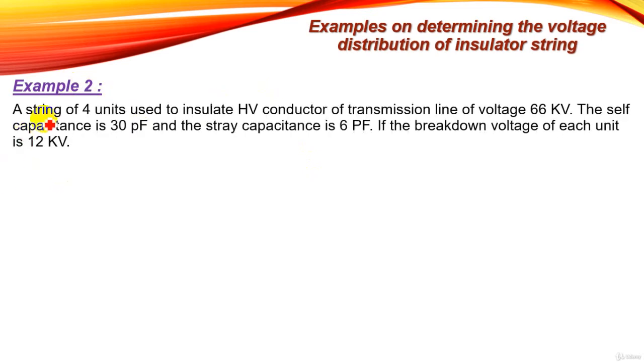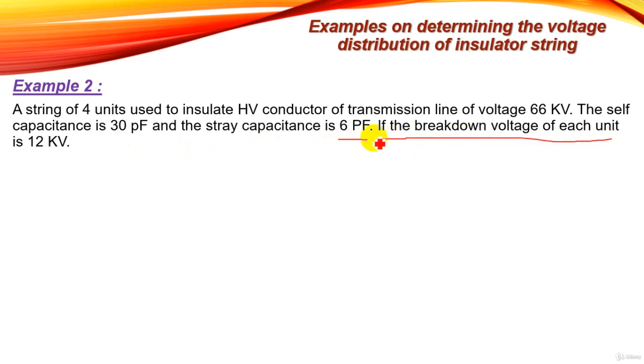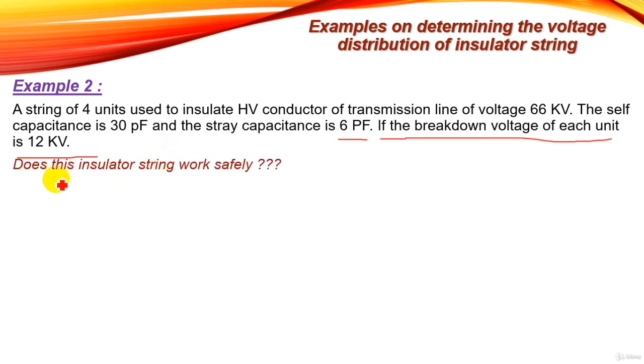Example 2: A string of four units is used to insulate a high voltage conductor of a 66 kilovolt transmission line. The self-capacitance is 30 picofarad and stray capacitance is 6 picofarad. Importantly, the breakdown voltage of each unit is 12 kilovolt — meaning each unit can withstand up to 12 kV; if exceeded, the unit will break down. Does this insulator string work safely?